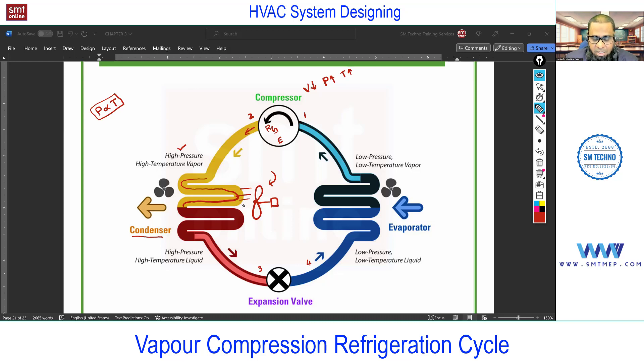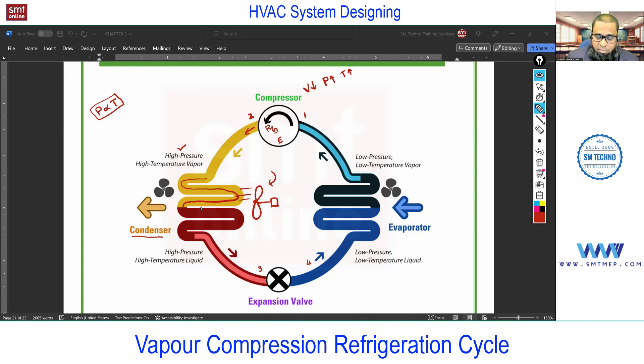As per the second law of thermodynamics, heat transfers from high to low. So the air is responsible to reject heat from this refrigerant, which is in the gas form, equal to the latent heat. The manufacturer will design this condenser to reject heat equal to the latent heat. When latent heat is rejected, the phase changes from gas to liquid. So the inlet of the condenser is high pressure and temperature vapor, and the outlet is high pressure and temperature but in liquid state.